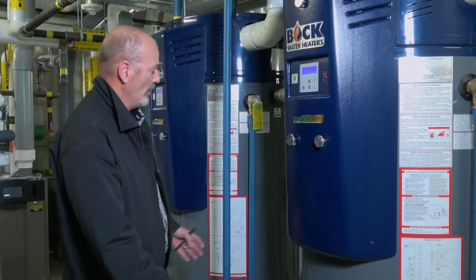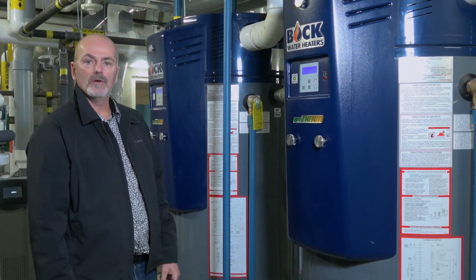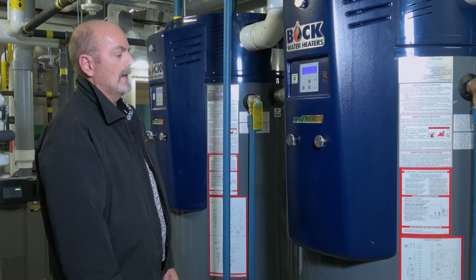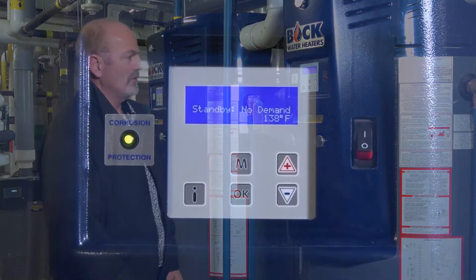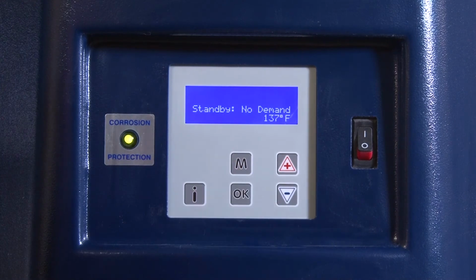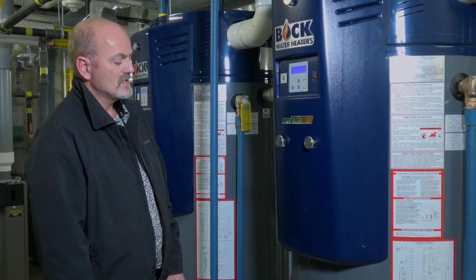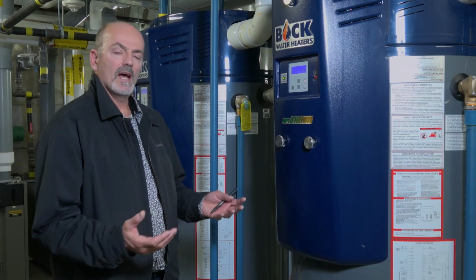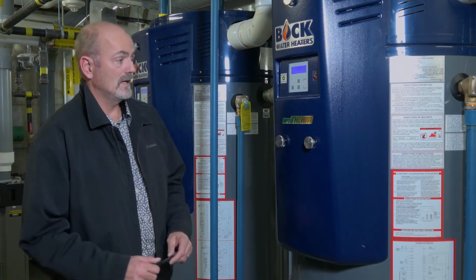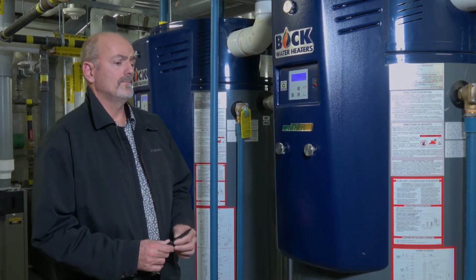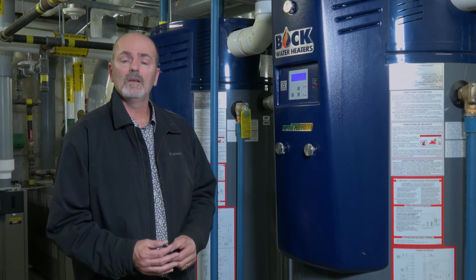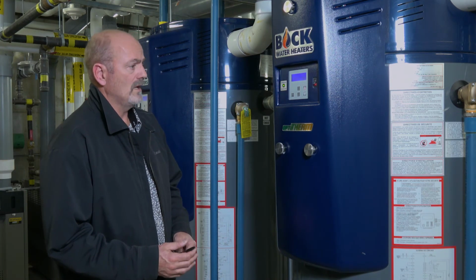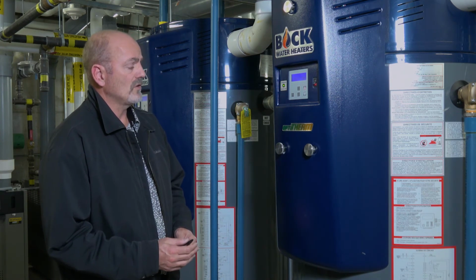Essentially what we have here are modulating condensing water heaters. There's two of them. They basically sense the temperature that's in the tank. They're set to maintain approximately 140 degrees. They are condensing and they use gas to heat. In terms of maintenance, it's something that again needs to be looked after by an authorized TSSA certified contractor, maintenance or installing.